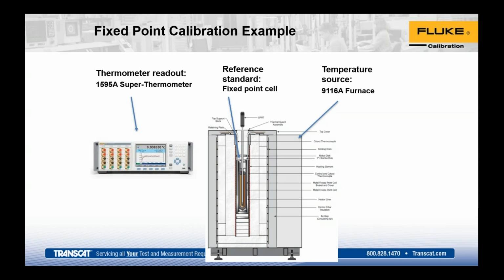One thing that's not shown here that's done at this level as well is that when metrologists are working through a fixed point process, they usually also have another secondary SPRT that follows the devices they're testing, or the new SPRTs, and they call that a check standard. So again, they're basically making sure that something doesn't go awry during the plateau process in the fixed point.